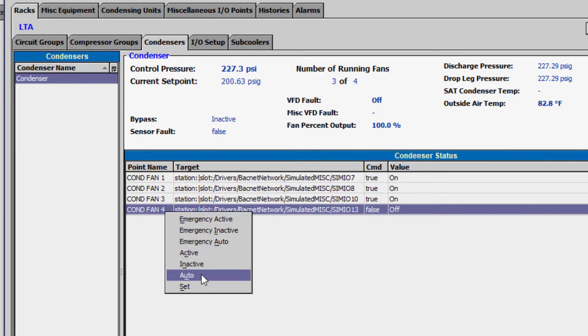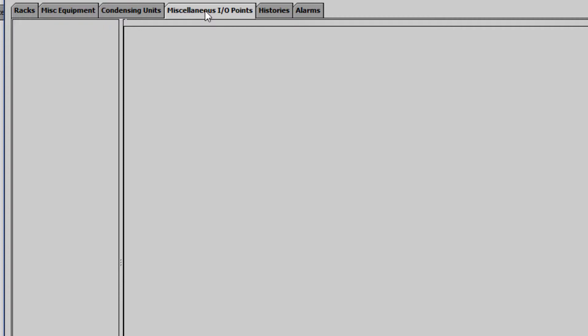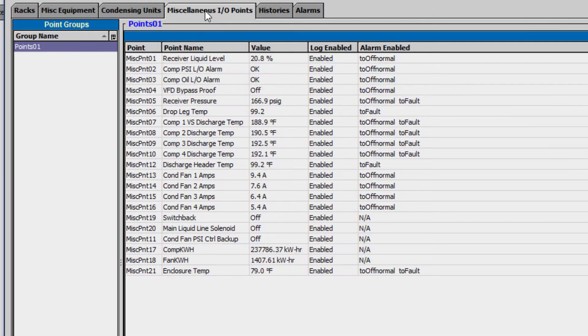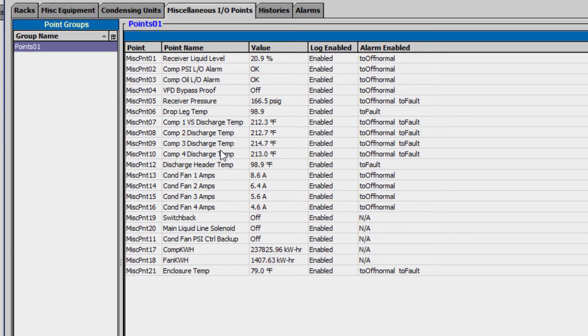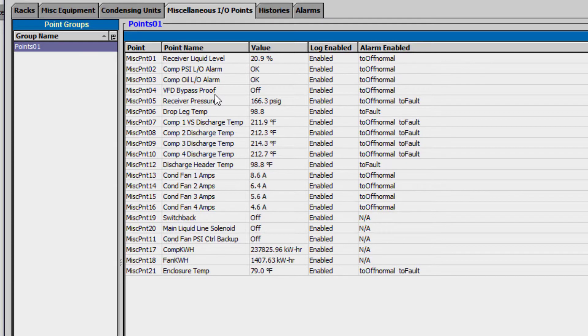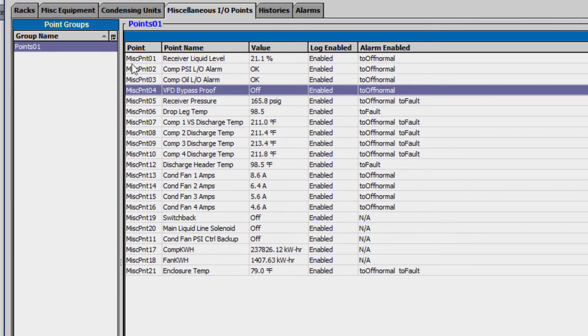Another place where you can find points to override is the miscellaneous IO tab. It is important to again note that while you can override some inputs and outputs here, it is best practice to avoid overriding inputs as they may affect multiple outputs. A better option is to either override outputs directly or, if testing a sequence of operation, to manipulate the cut-in and cut-out values to observe the anticipated controlled operation.